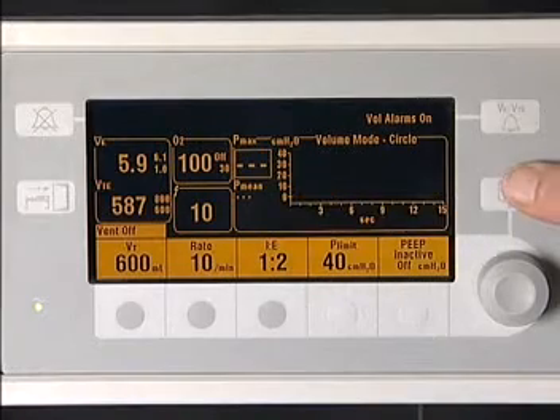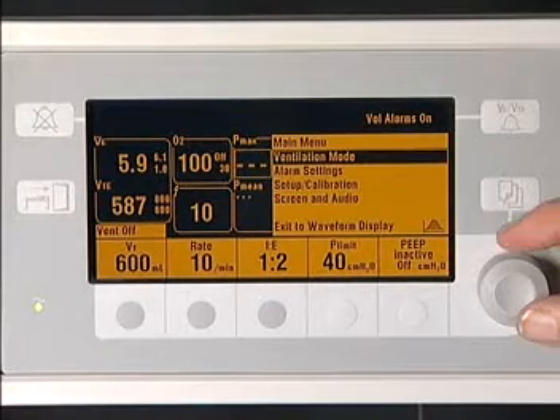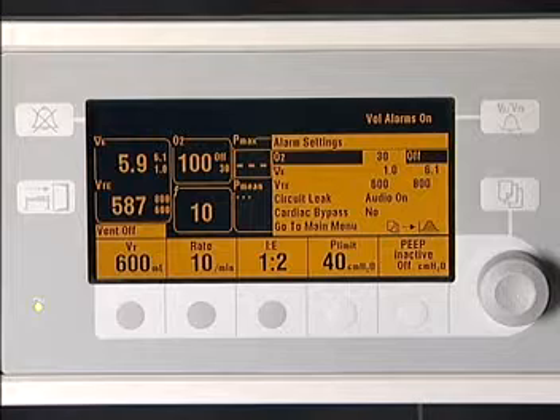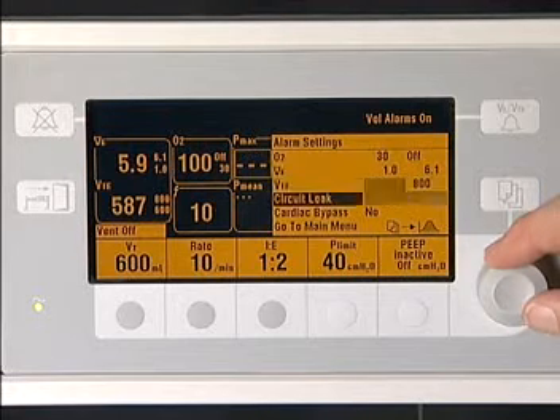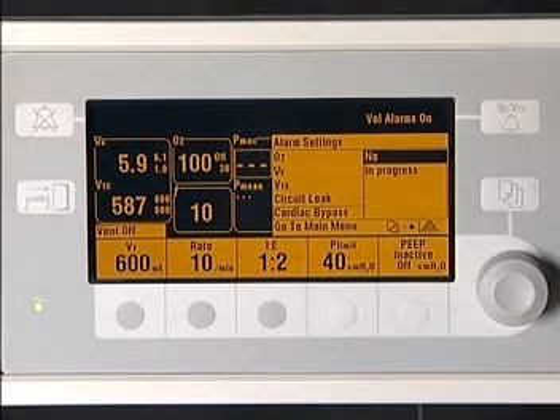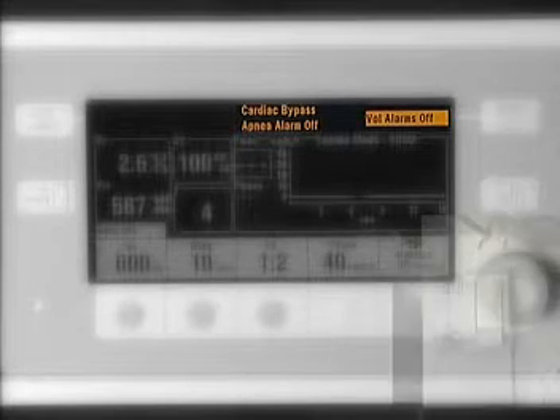Another menu selection is Cardiac Bypass. This selection allows cessation of apnea and volume alarms and prevents manipulations of the chest to be detected as breaths, resulting in false positive alarms. The Aestiva considers volumes as small as 5 ml as breaths, since they are attainable in the pressure control ventilation mode. These breaths will start the 30-second apnea alarm if the apnea alarm is not disabled. This selection will be disabled when mechanical ventilation is chosen or end case is confirmed.